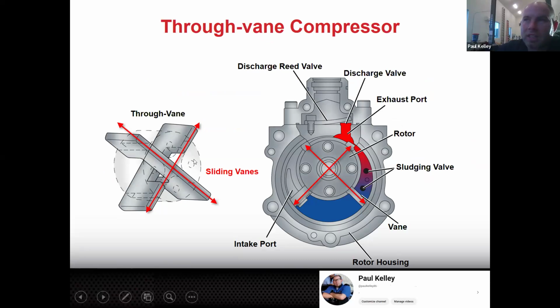This type of compressor is one of the worst ones to fail because the vanes will wear and send metal all through the system, which they can all do. This is a good design, easy to understand, but it definitely has the potential where if you have a compressor failure, this metal can end up getting pushed out the discharge and into everything.